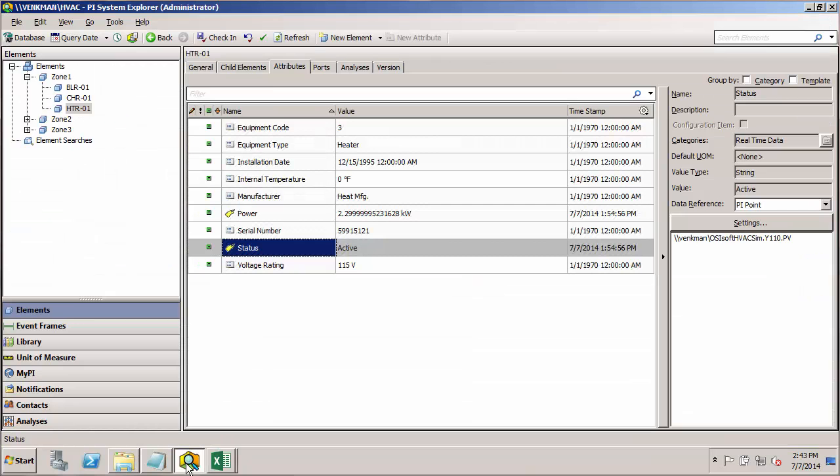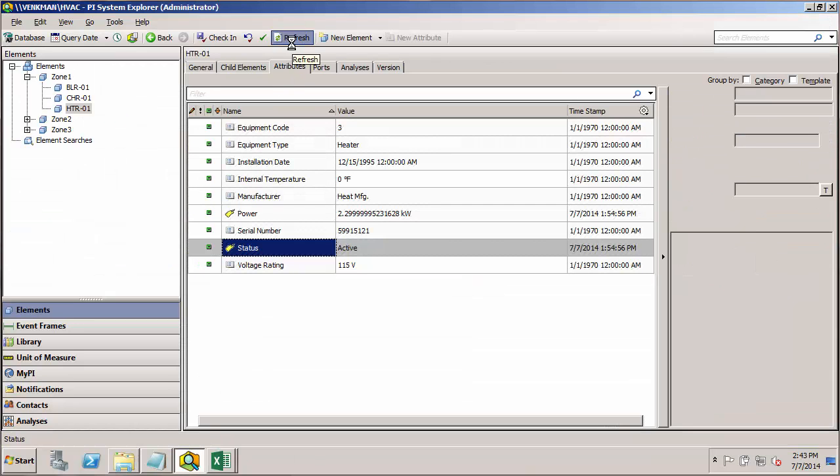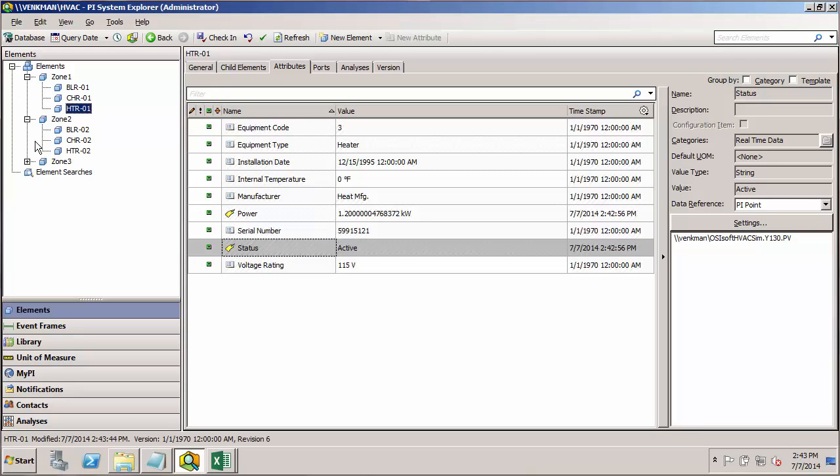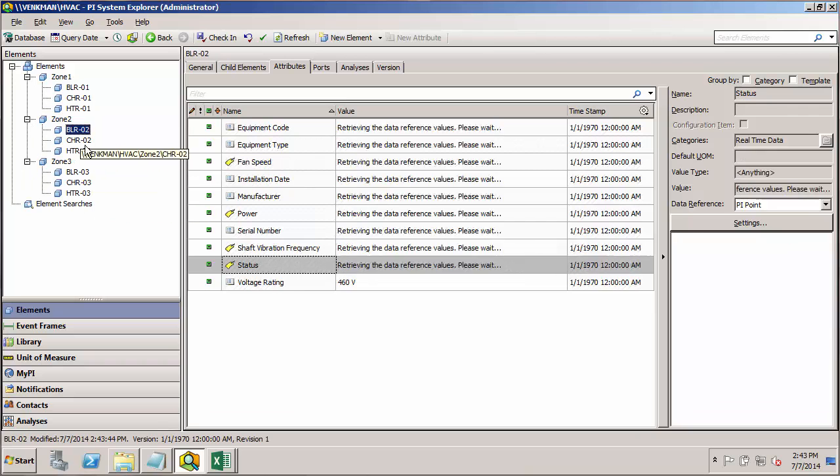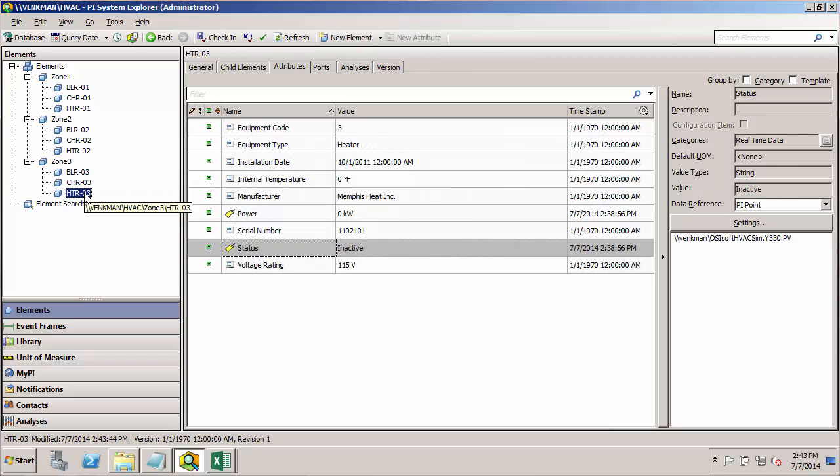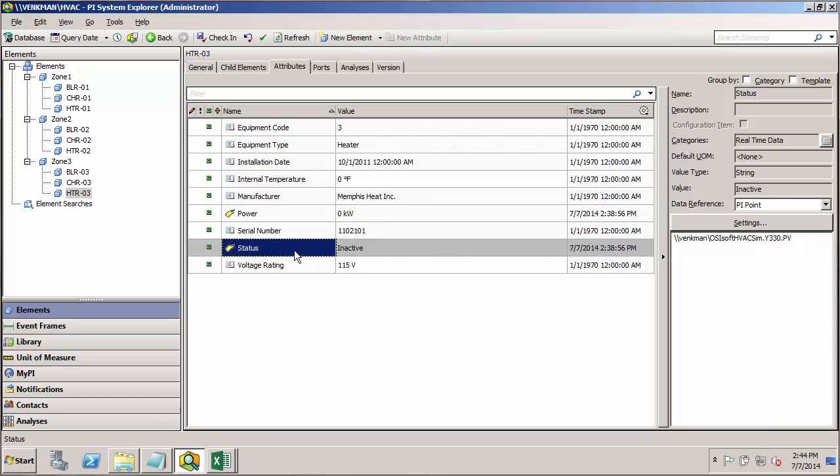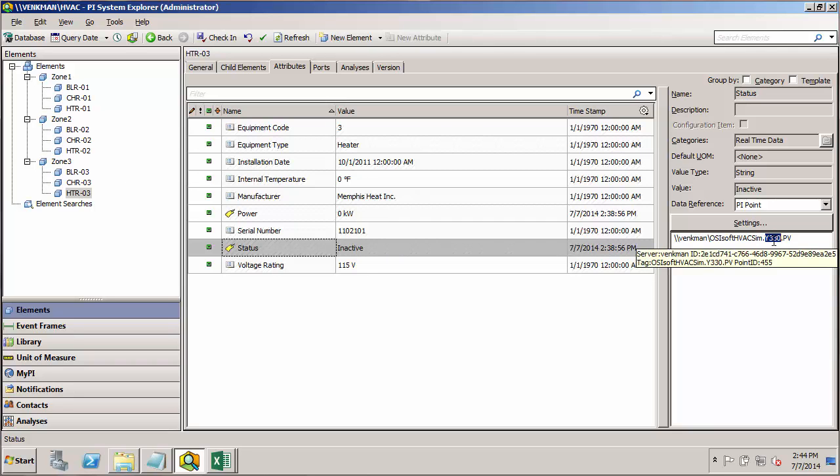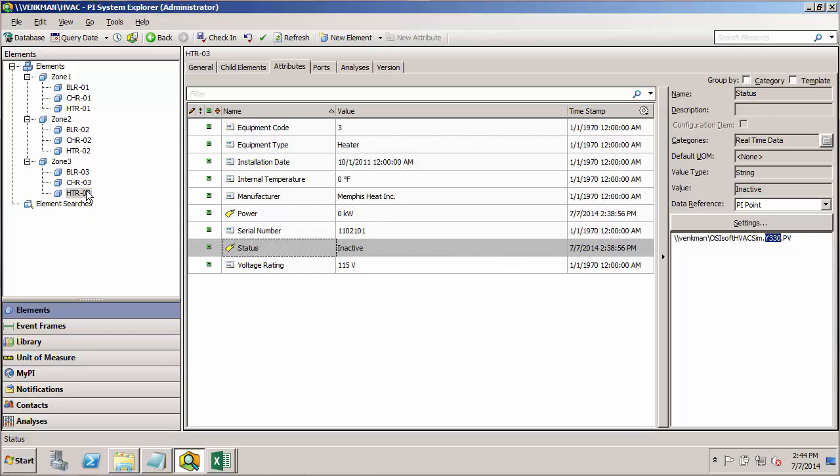If we go back to PI System Explorer and do a refresh, now we see that we have elements for all of our equipment under zone 2 and zone 3. And we can see here that say for the status of the heater in zone 3 using the Y330 tag, which is correct. Y being for the status tag, the first 3 being for the zone, zone 3, and the second 3 being for the heater.